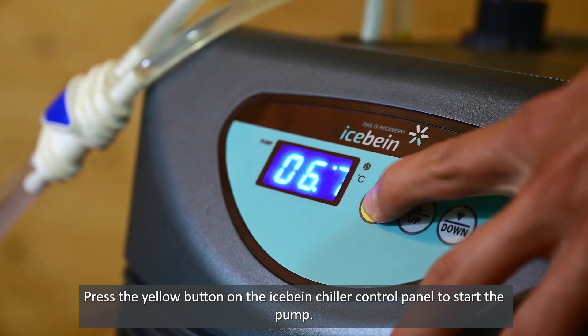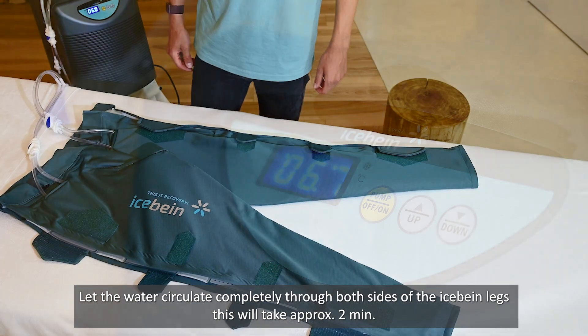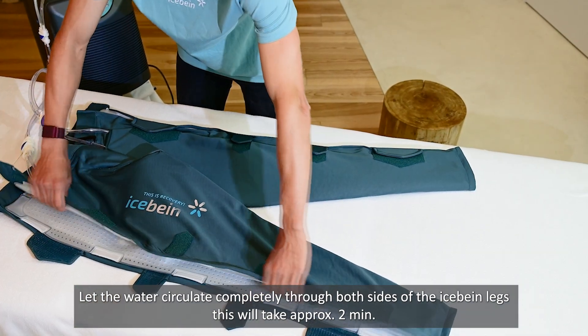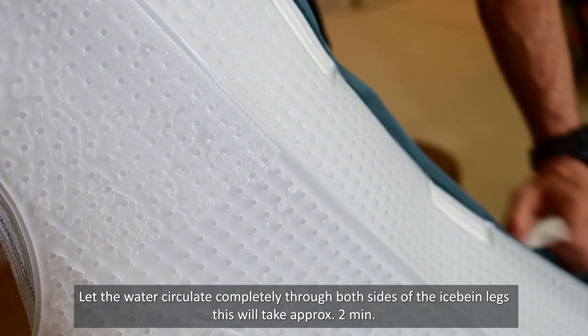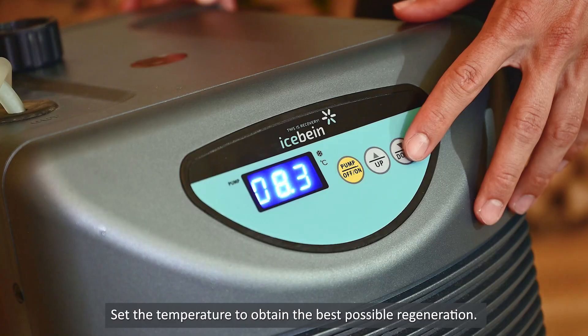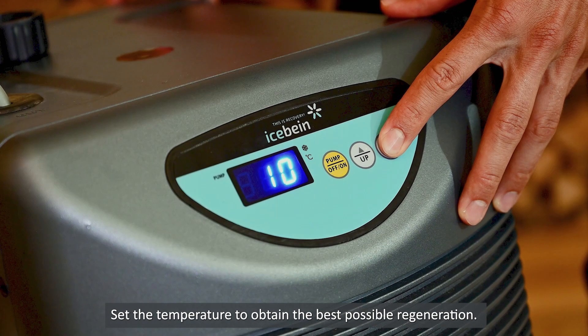Press the yellow button on the icebein chiller control panel to start the pump. Let the water circulate completely through both sides of the icebein legs — this will take approximately 2 minutes. Then set the temperature to obtain the best possible regeneration.